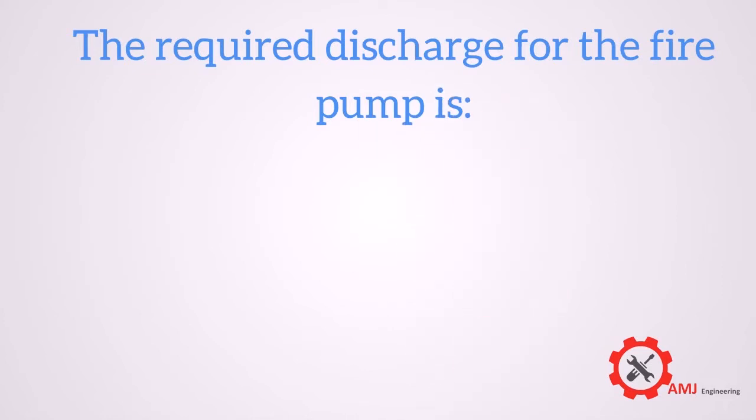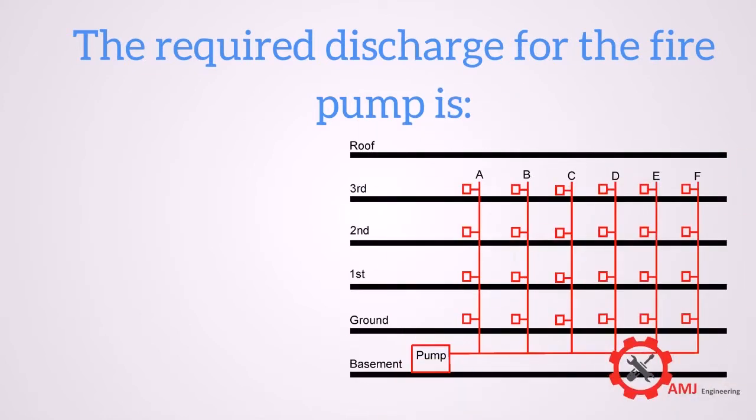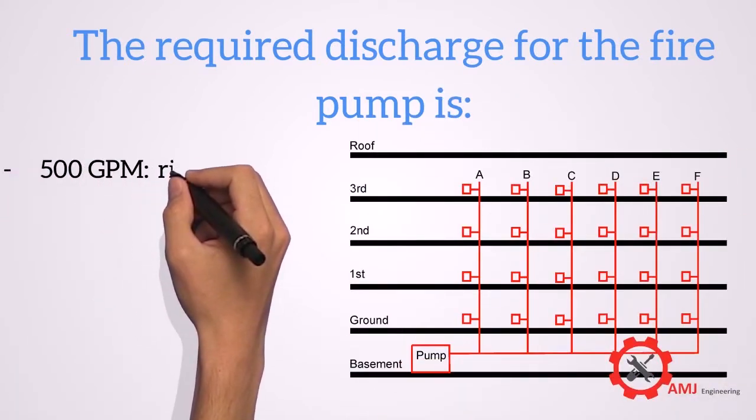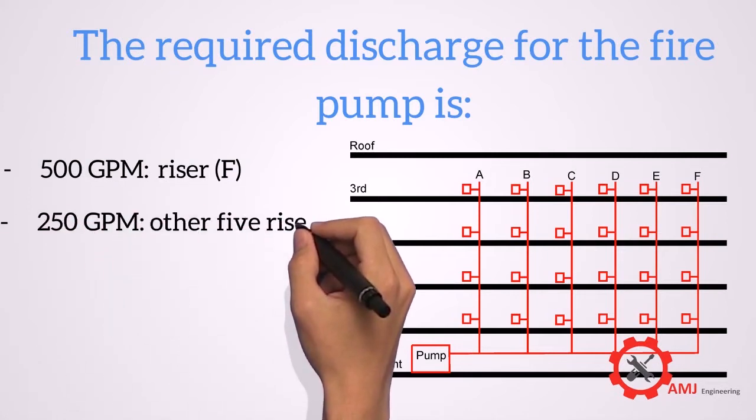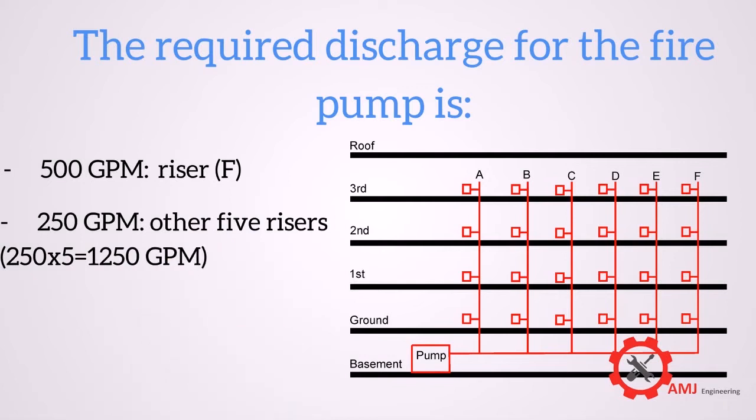The required discharge for the fire pump is: 500 GPM required for the most remote riser, and 250 GPM required for each riser of the other 5 risers.